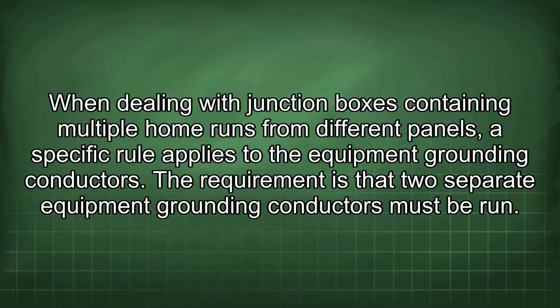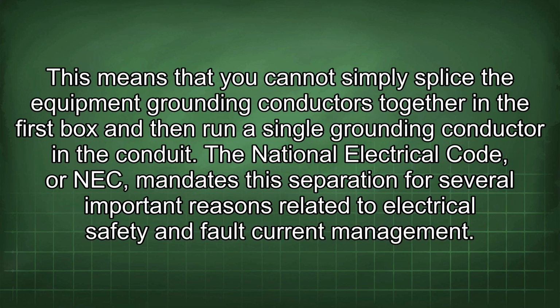When dealing with junction boxes containing multiple home runs from different panels, a specific rule applies to the equipment grounding conductors. The requirement is that two separate equipment grounding conductors must be run. This means that you cannot simply splice the equipment grounding conductors together in the first box and then run a single grounding conductor in the conduit.